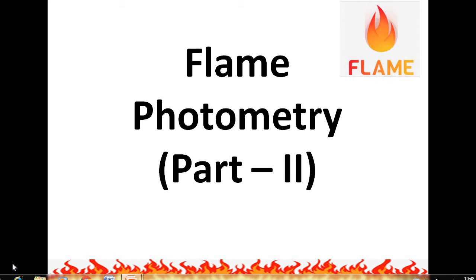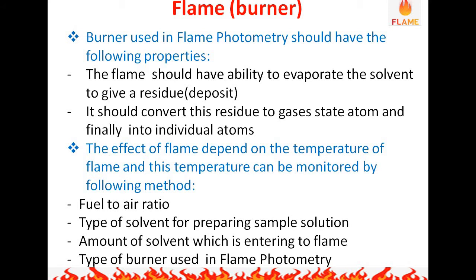The burner used in flame photometry should have the following properties: the flame should have the ability to evaporate the solvent to give a residue, and it should convert this residue to gaseous state atoms and finally into individual atoms. The flame temperature can be monitored by the fuel-to-air ratio, the type of solvent used for preparing the sample solution, the amount of solvent entering the flame, and the type of burner used.